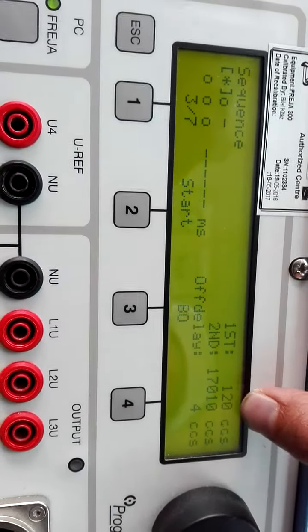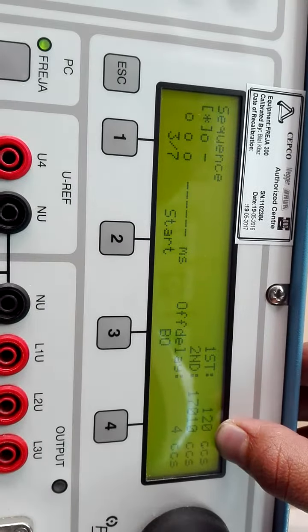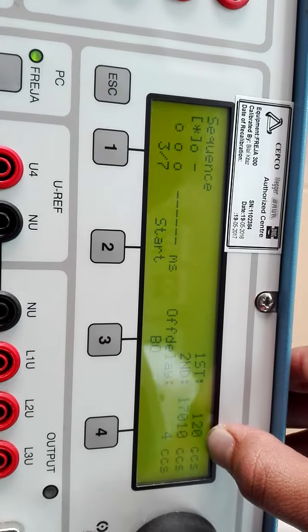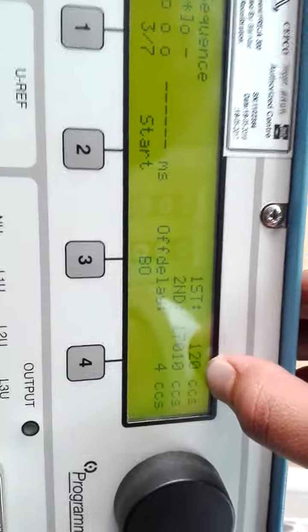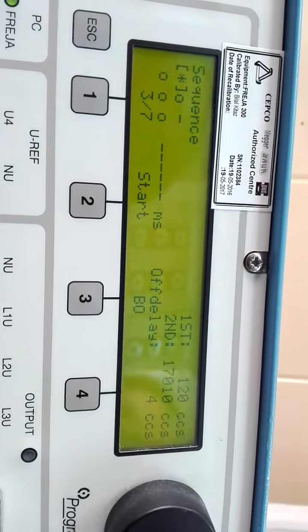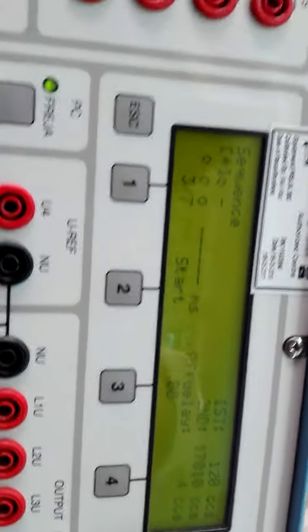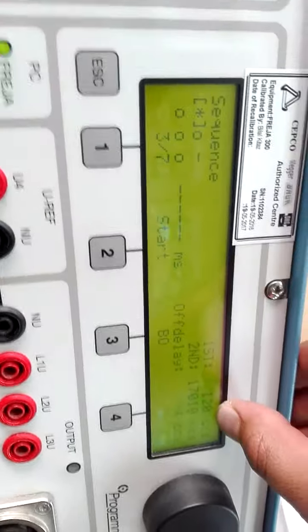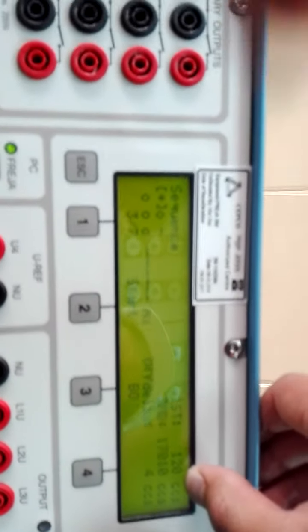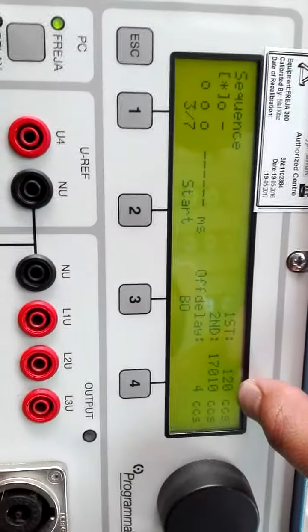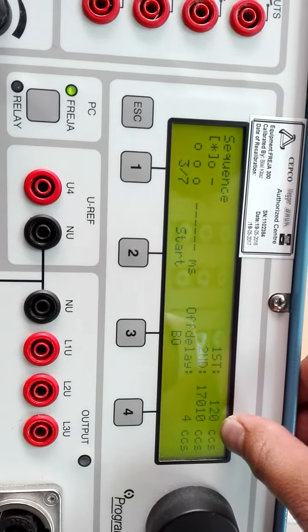Okay, so it is always advised to set the first page for some time, to give the FREJA some time to not measure. For example, if you connect it to a relay, the relay may take some time, maybe 30 milliseconds or 50 milliseconds. The relay will take time to coordinate with the other equipment. So this time is always required for some equipment. You may select 60 cycles, to give some time to make the other relay which is connected to your FREJA ready. After this, the consideration starts. So maybe 40 cycles, 60 cycles, 80 cycles, different for different kinds of relays.